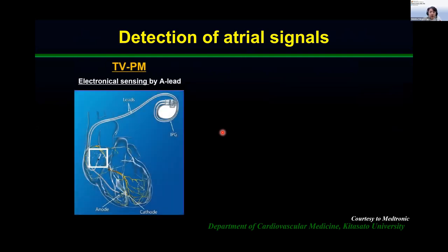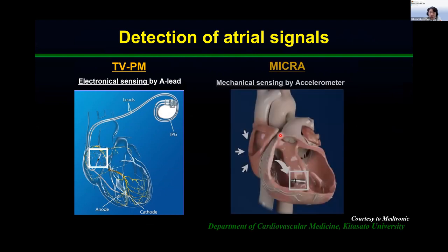Let me explain the detection of atrial signal between the transvenous pacemaker and Micra. As you know, the transvenous pacemaker can detect atrial activation by electrical sensing with an atrial lead. On the other hand, Micra can detect the atrial signal by mechanical sensing via an accelerometer on the device.